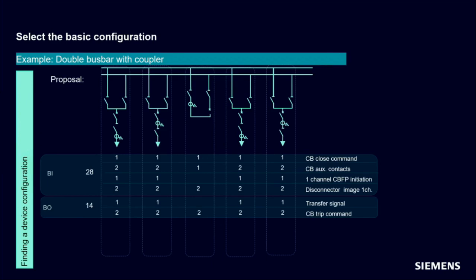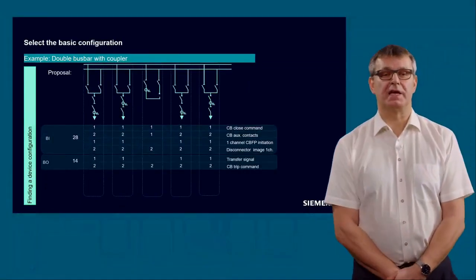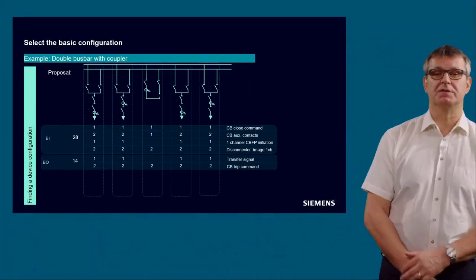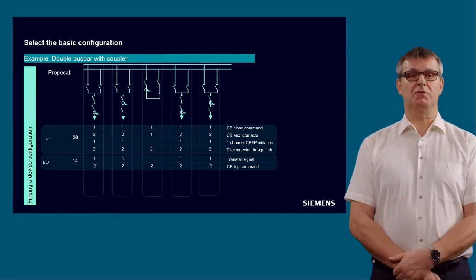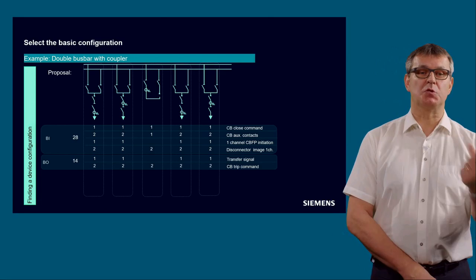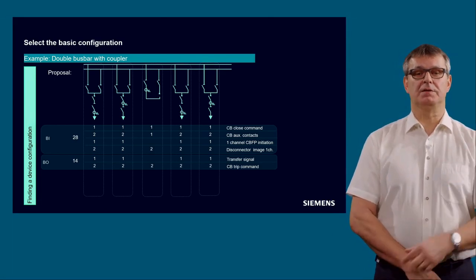Binary outputs. How many binary outputs do we need? We have this transfer signal from the end-fault protection to send a trip signal in case of a fault between the circuit breaker and the current transformer to the other end of the line. So we need 1 binary output, typically not necessary in the coupler, because you have no other end of the line in a coupler. And typically for the circuit breaker trip command, we are using 2 binary outputs. So in total, we need for this configuration 28 binary inputs and 14 binary outputs.